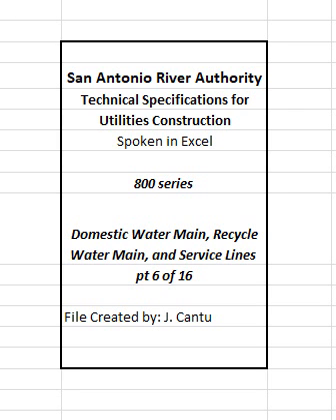Not more than 500 feet of trench shall be opened between the trench cutting and the trench backfilling, except as otherwise directed. The contractor shall make exploratory cross-cuts ahead of pipe-laying operations to verify grades of other underground utilities and shall gradually adjust the depth of excavation to clear such utilities.